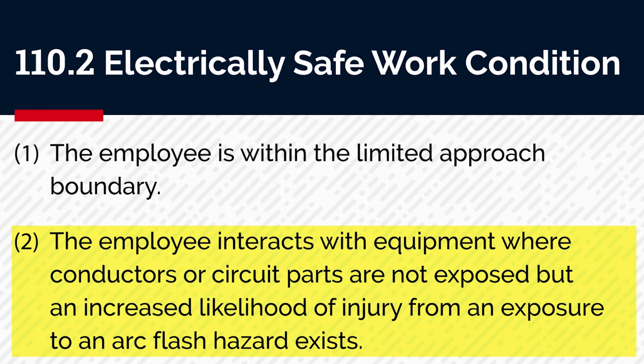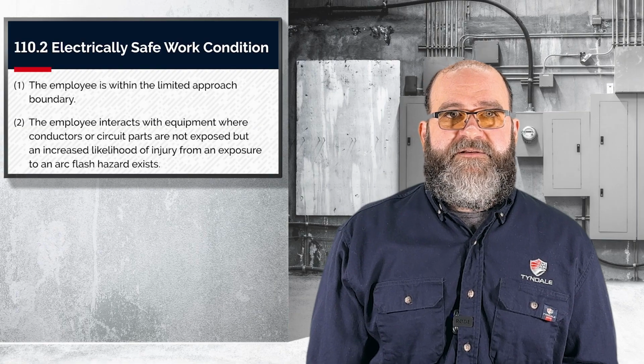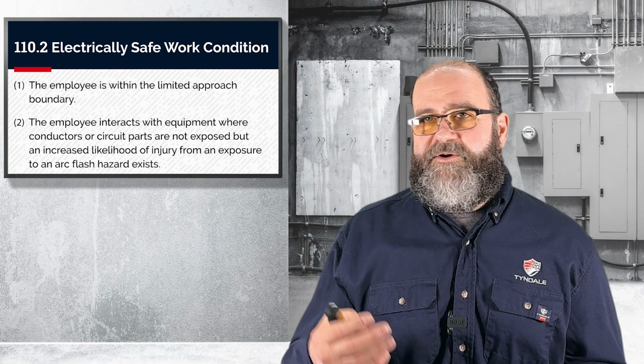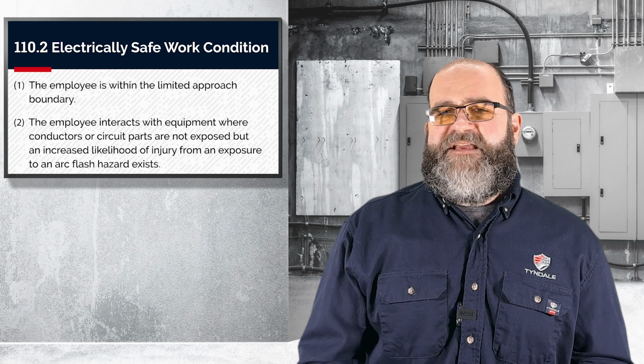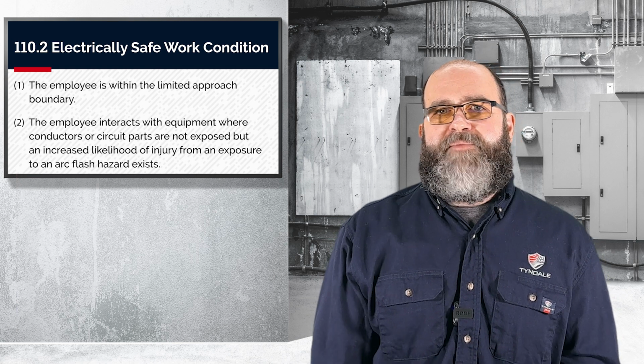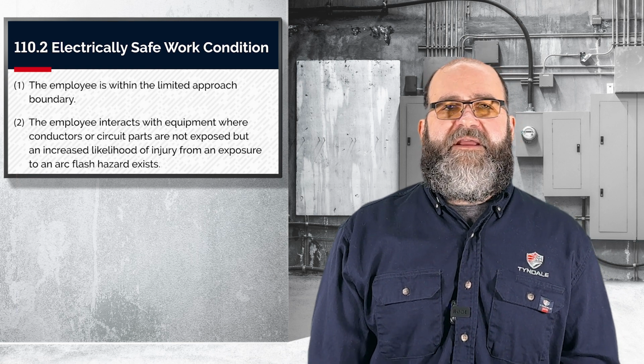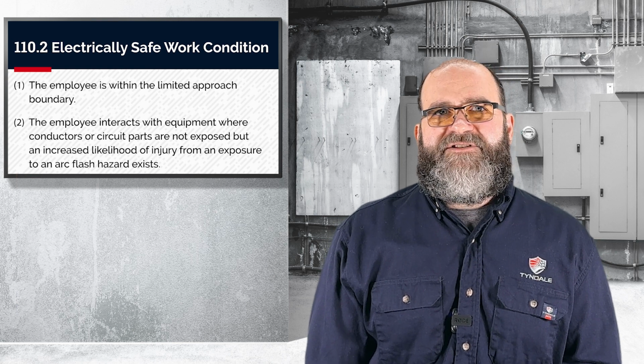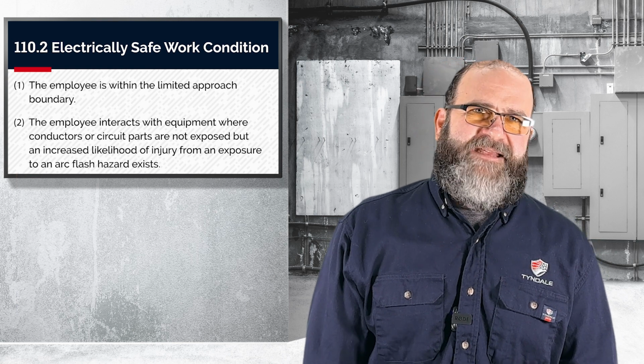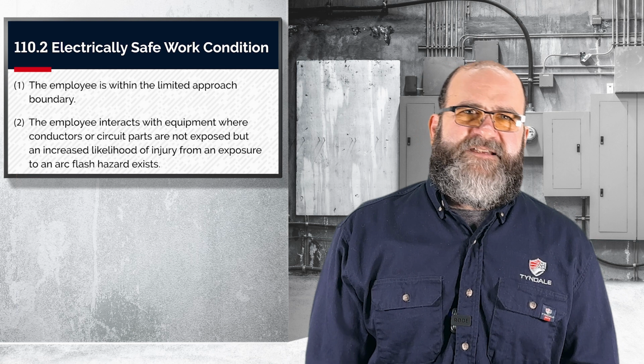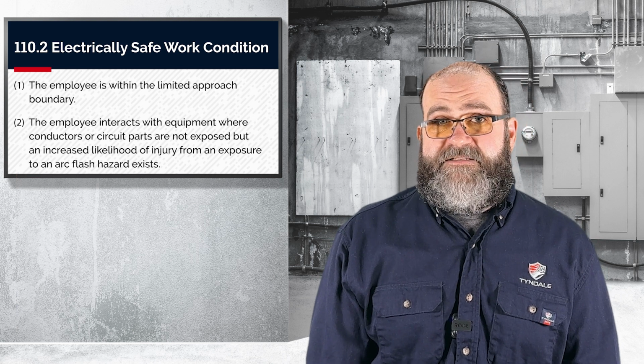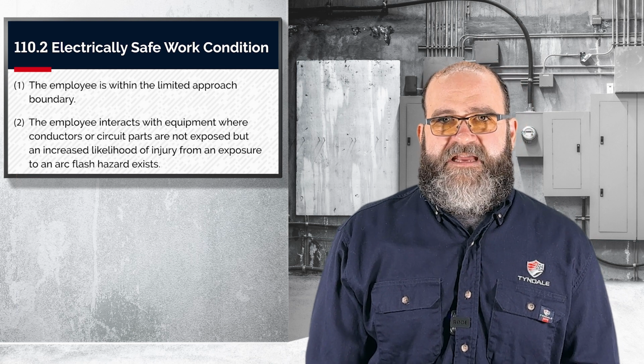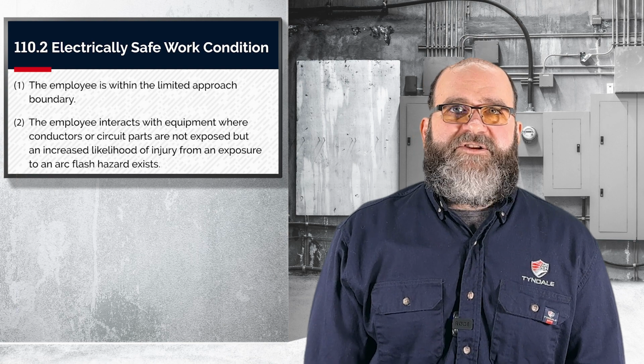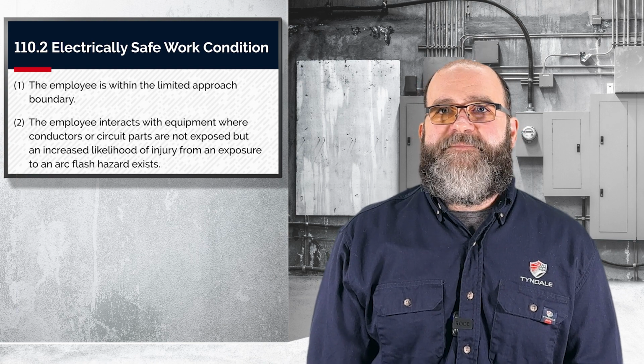What does interacting mean? Interacting could mean resetting breakers, pushing buttons, resetting motor starters, turning disconnects on and off, etc. I'm sure that you can fill in that blank with several of the tasks that you do daily at your job. Now, does that mean that you need to go put on PPE, de-energize, fill out risk assessments and all that to do these tasks? Well, the answer is exactly maybe. When we start getting into this text, we find some exceptions.